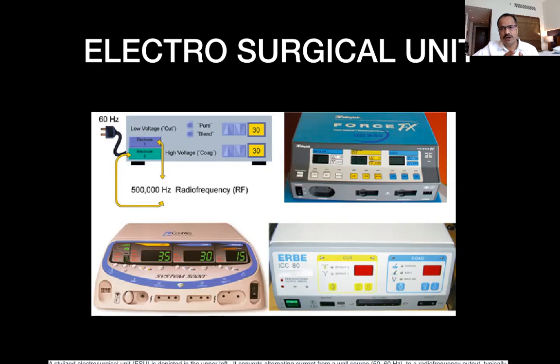And that is also called radio frequency because that is where the transistors or the radio work. So it converts 60 Hertz into 300 kilohertz. So the ability of this electrosurgical unit to convert it to so high, where the muscles and nerves will no longer be depolarized, allows us to use this in our day-to-day surgeries.